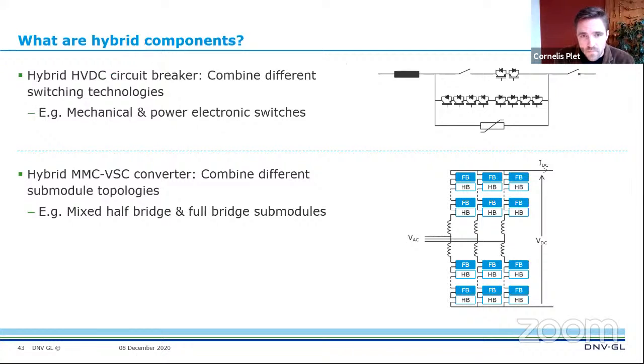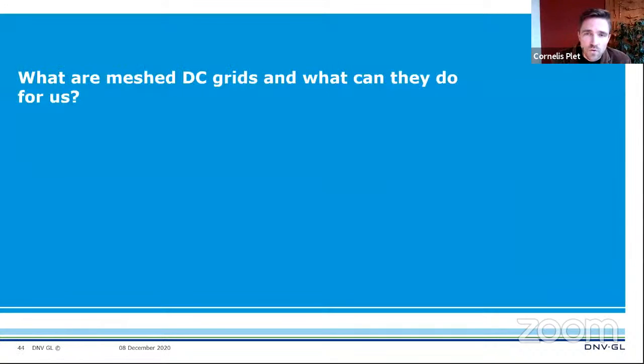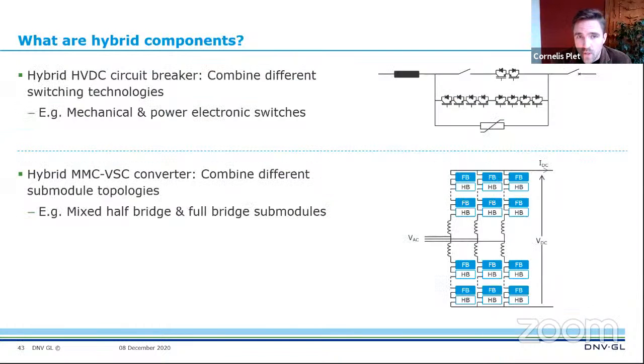Next slide, please. There are also two types of hybrid components in HVDC grids. One famous one is the hybrid HVDC circuit breaker, which combines the low cost, low loss, and high dielectric withstand properties of mechanical switches with the high speed of operation and controllability of power electronic equipment. The technology for such equipment works. We tested a 350,000 volt version in the promotion project, and several similar types are in operation in China today. The challenge in getting those things to work is the system integration - how do you integrate a DC circuit breaker in a multi-vendor setting with, at the moment, no guidance from a DC system grid code in place?